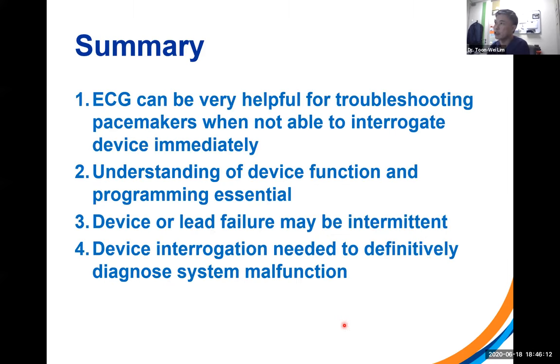So in summary, I think the ECG can be very helpful for troubleshooting pacemakers, especially when you're not able to interrogate the device immediately. This is particularly helpful for my emergency colleagues, who can tell a lot about what's going on before we actually interrogate the device. Understanding of device function and programming is essential to help you troubleshoot using an ECG alone. Just be mindful that device and lead failures can be intermittent at times, but ultimately you'll need to interrogate the device to definitively diagnose system malfunction. Thank you for your attention.